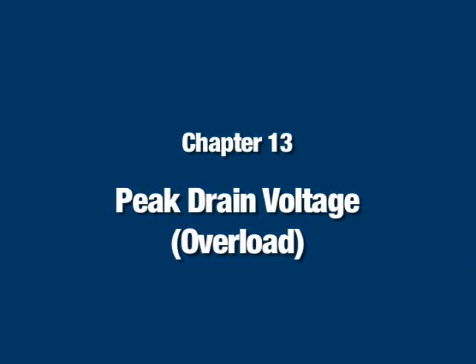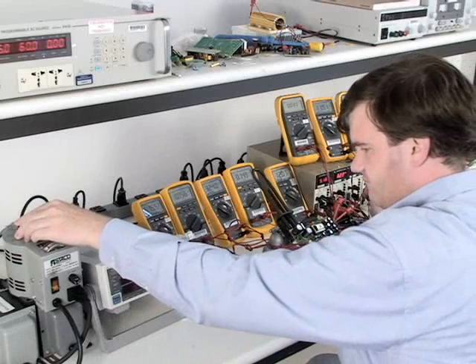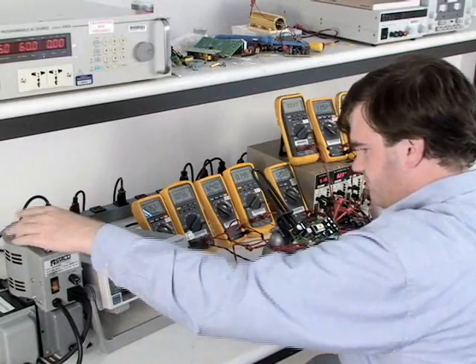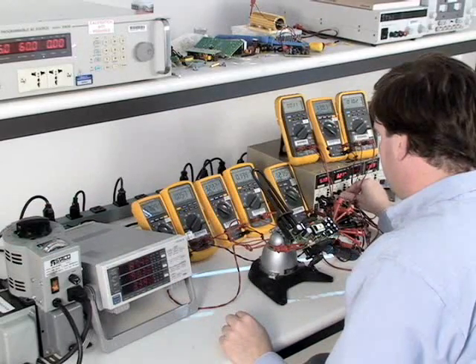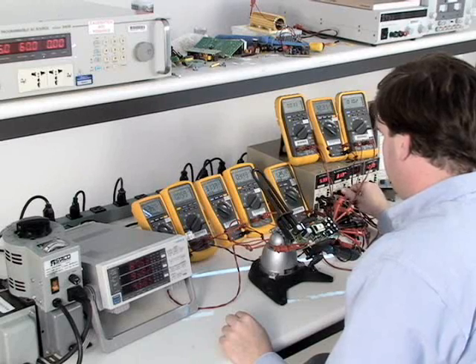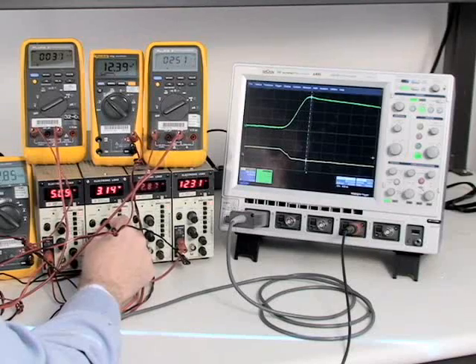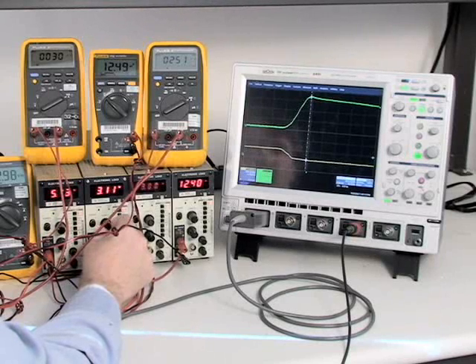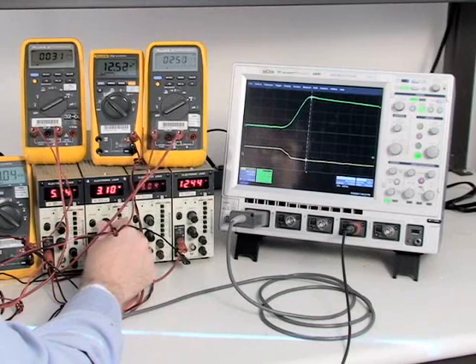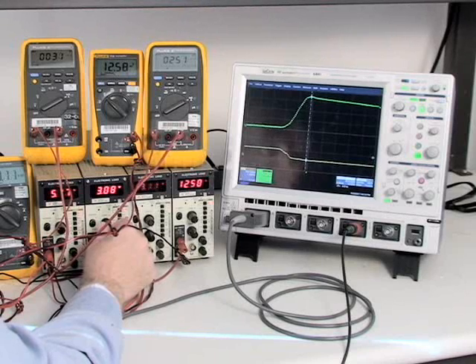Chapter 13, Peak Drain Voltage Overload. After the power supply starts up, increase the AC voltage to the minimum input voltage and load the supply to full load. On the primary output, slowly begin increasing the load while monitoring the peak drain voltage on the scope. As you begin overloading the power supply output, verify that this peak voltage never exceeds 650 volts peak. If it does, stop the test and debug your clamp circuit.